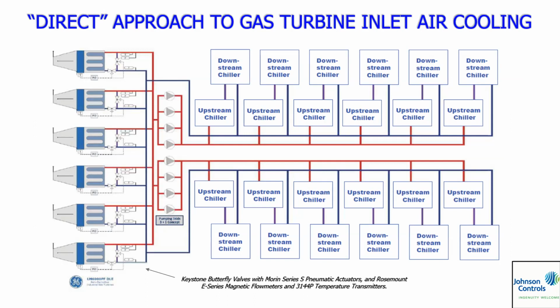Everything's in series. And then on the pumping, we had N+1, really we had 3 pumps doing the duty with 1 standby, okay, for each bank of chillers. And then at the turbines, we had constant pumping. Now, there's some discussions on that, but constant pumping, we're doing constant flow. And then at the turbines, we'd have bypass. Okay, so it always delivers constant flow. And if we didn't need the water to maintain a certain temperature entering the turbine, we just bypassed it and we brought it back. So basic piping.